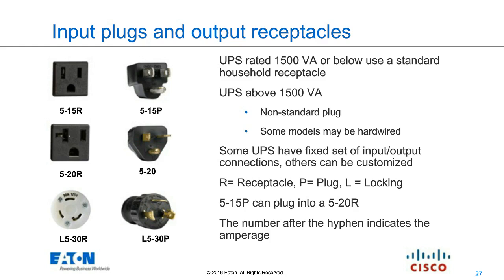It's going to limit you to about 1,500 VA. Really, it's about 1,400 watts, which is really what we talk about in the white space is wattage. Nobody cares about volt amps. And that's assuming that it's 120 volts. That NEMA 5 designates that this can only be energized to 120 volts. So to the question, a converged blade, really the biggest consideration there is density. And in most cases, a 515 or even a 520 is probably going to come up a little bit short of what this blade is actually going to need. So now we're jumping up into the 30 amp, and that's where we're getting up to about the 3,000 watt mark. And of course, that L in there is going to designate the locking plugs, and that's a great thing whenever you don't want your equipment to accidentally get unplugged.